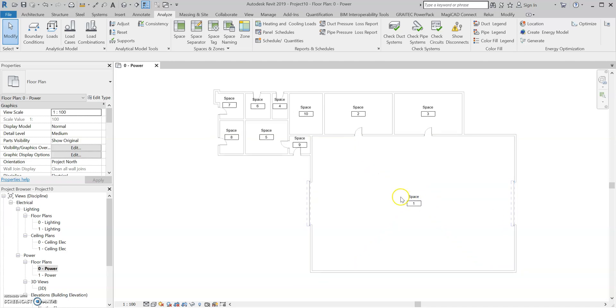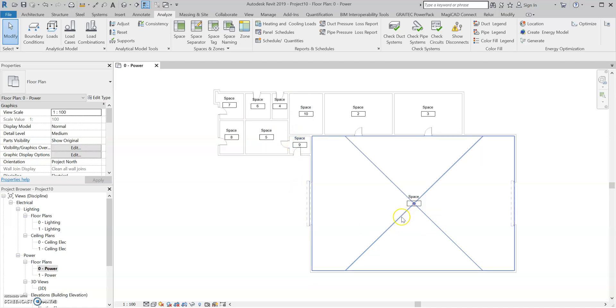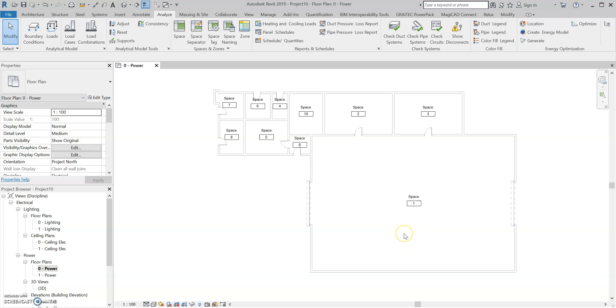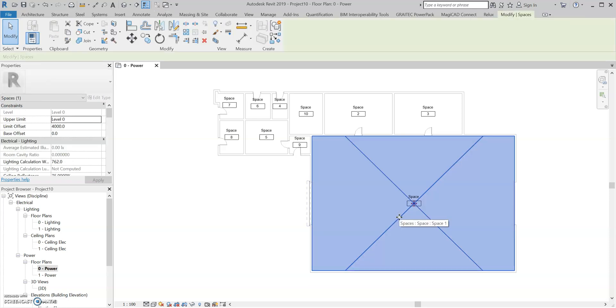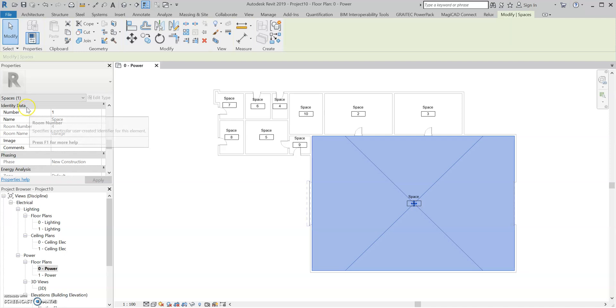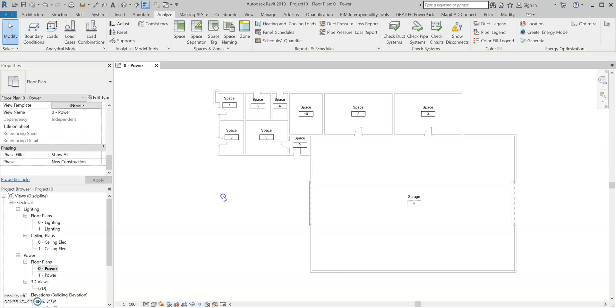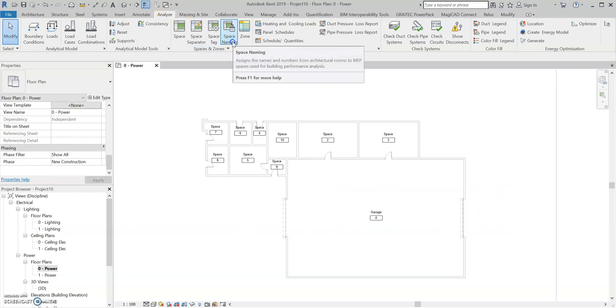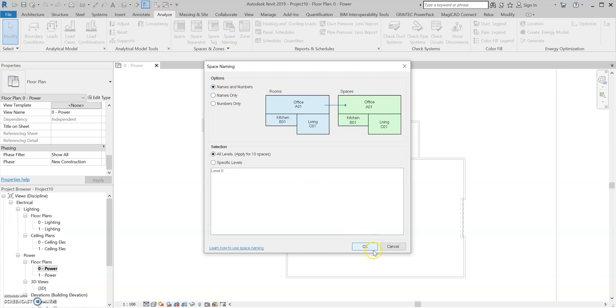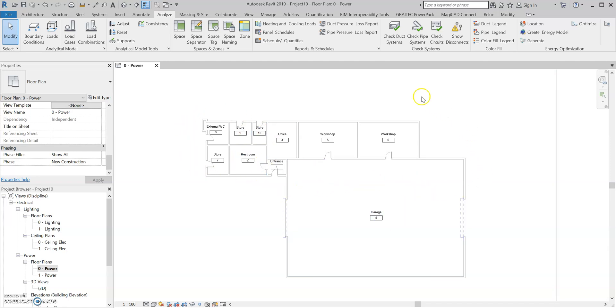So now we've got our spaces in — space one, space two, etc. We want these to match the architect's rooms. If we select the space, and you'll know you've selected it when it comes up with Spaces in the properties, we're going to scroll down and you'll see under Identity Data the room name and number. To get the space name and number to match, we can either type it in manually, or you can go to Analyze, Space Naming, Names and Numbers, and select OK. That will change all the space tags to the correct room name and number.